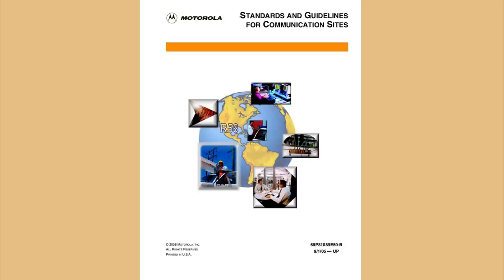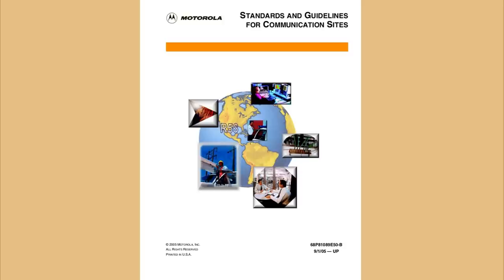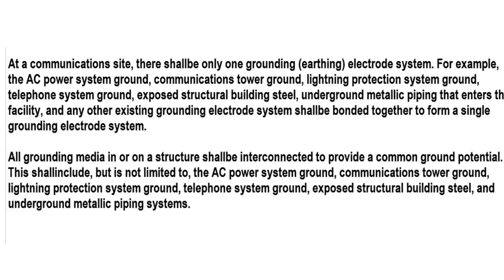Motorola has written a book on grounding equipment. And it says, at a communications site, there shall be only one grounding earthing electrode system. And it means one grounding system for everything. They're all tied together.